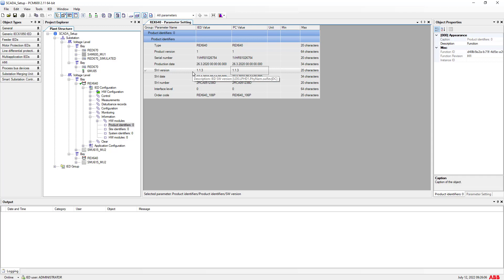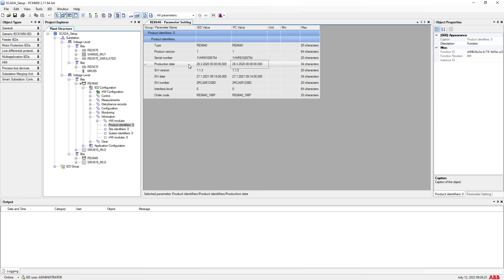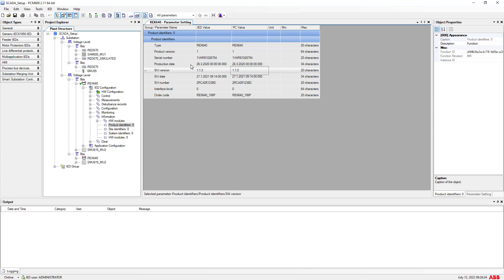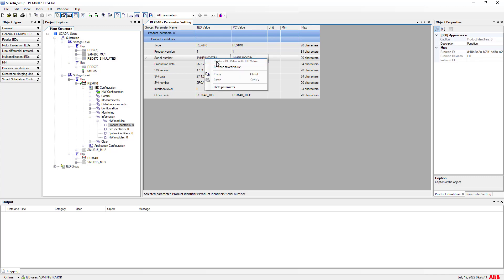We can now see the existing version in our IED is 1.1.3. The serial number is very important in order to check the firmware availability for this particular IED. We can also see the production date for the currently installed firmware — version 1.1.3 was produced around 2020. Just right-click the serial number and copy it.